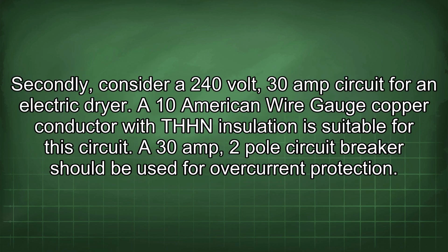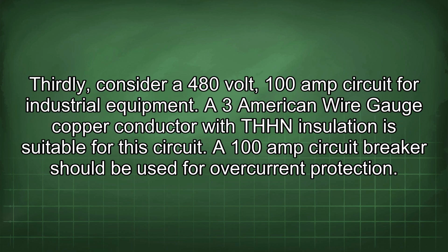Secondly, consider a 240 volt, 30 amp circuit for an electric dryer. A 10 American wire gauge copper conductor with THHN insulation is suitable for this circuit. A 30 amp, 2-pole circuit breaker should be used for overcurrent protection. Thirdly, consider a 480 volt, 100 amp circuit for industrial equipment. A 3 American wire gauge copper conductor with THHN insulation is suitable for this circuit. A 100 amp circuit breaker should be used for overcurrent protection.